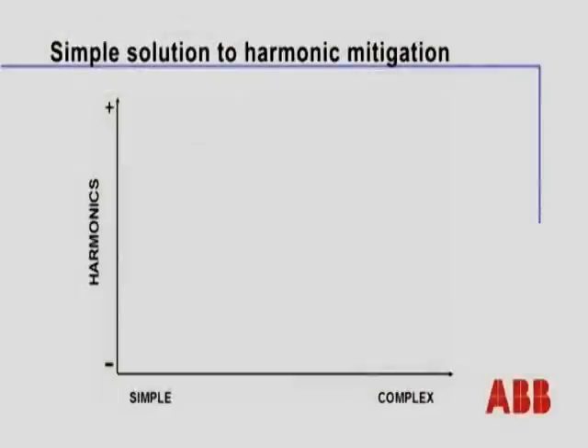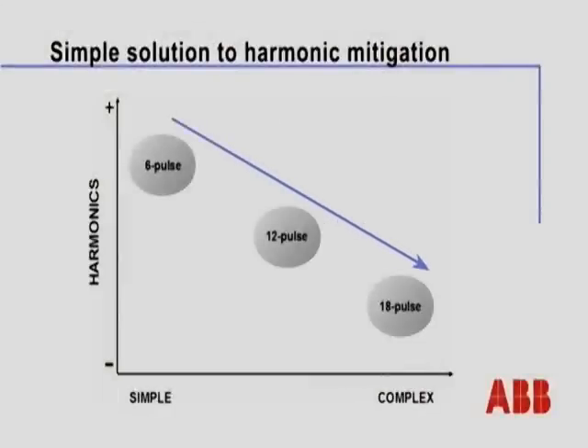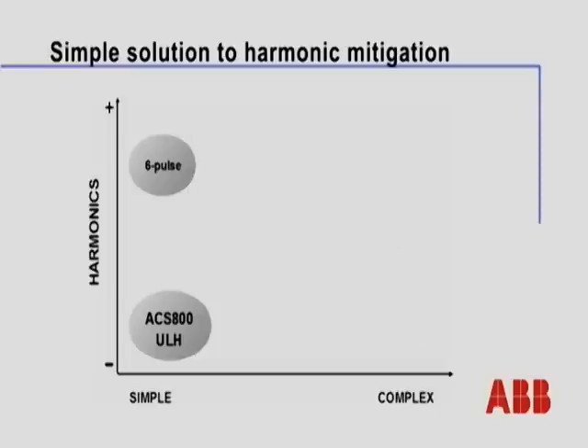We're always looking for the simplest, most effective solution to our problems. This doesn't differ in harmonic mitigation. It seems as though the effectiveness of the solution always seems to add complexity to the solution. With the ULH, we've broken that mold. We go from 6-pulse to 12-pulse to 18-pulse to ultra-low harmonics, the highest level of harmonic mitigation available, but we've taken a back step all the way down to 6-pulse levels in terms of simplicity of the solution.